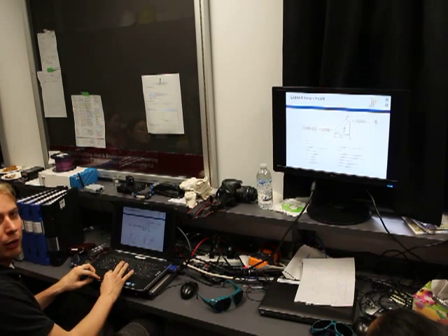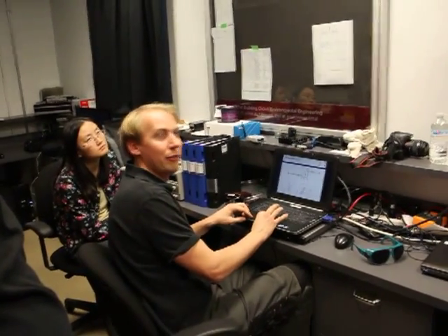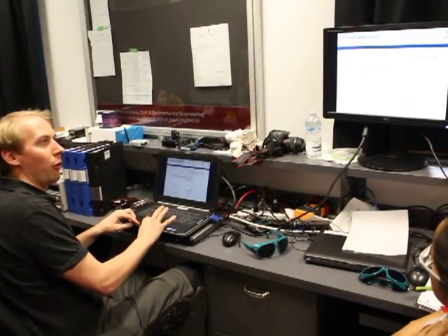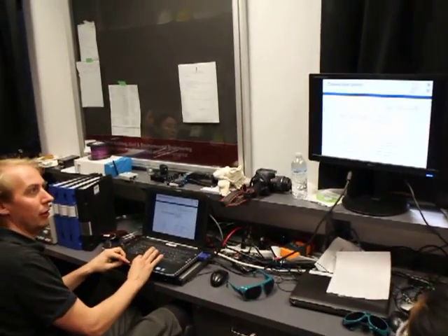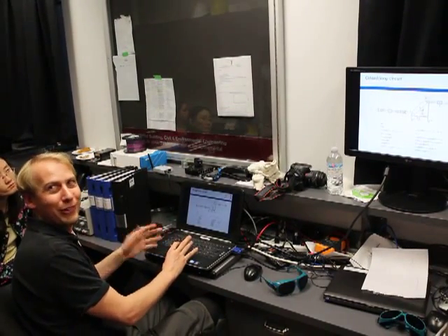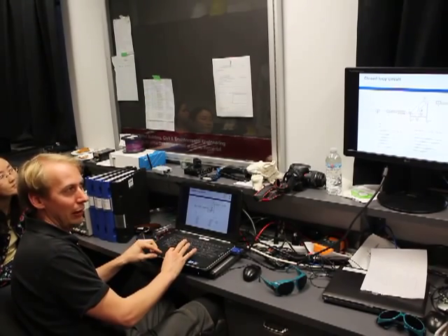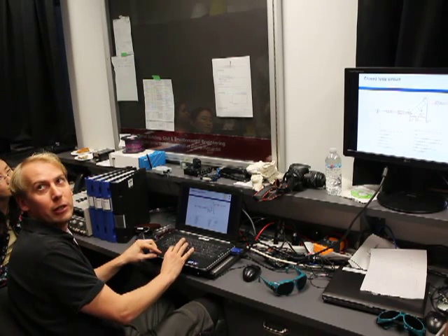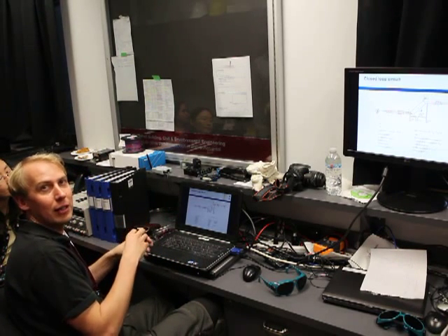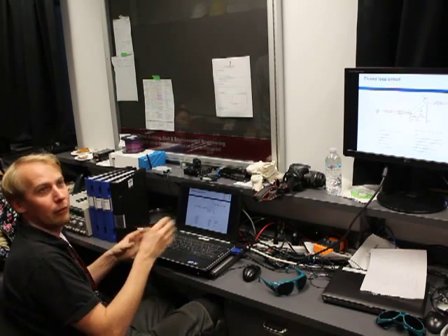But what they try to do is, you have under pressure on this side if the fan sucks air from here, and you will have overpressure over here if it blows in here. And what they try to do is to reach the ambient pressure at position 5, in the center of the collector, in order to have the least possible leakage rate of the collector. So this is why they use two fans.